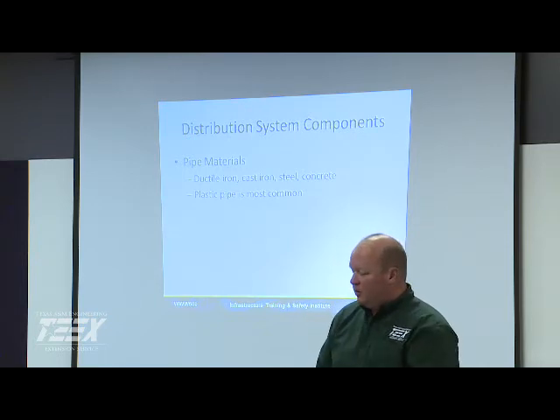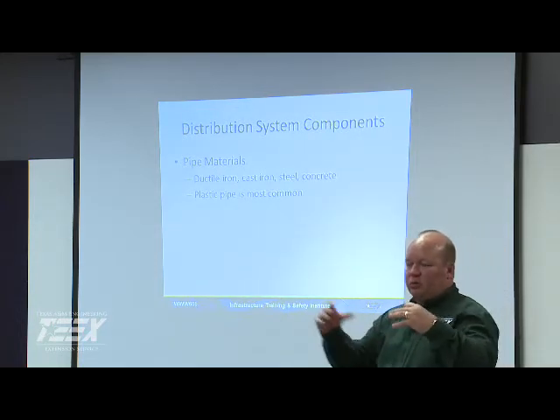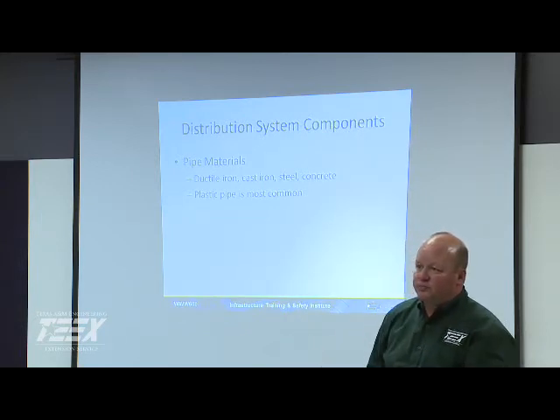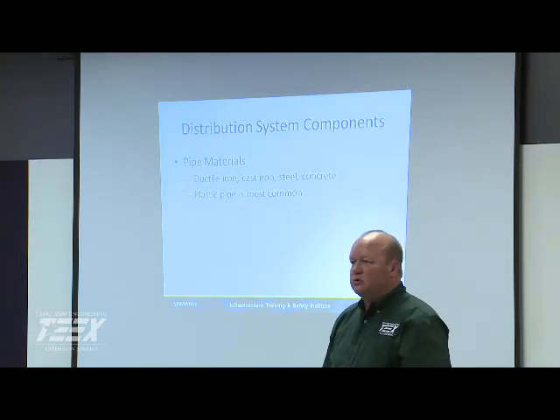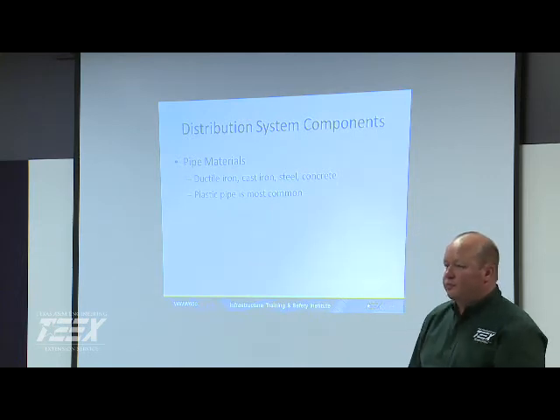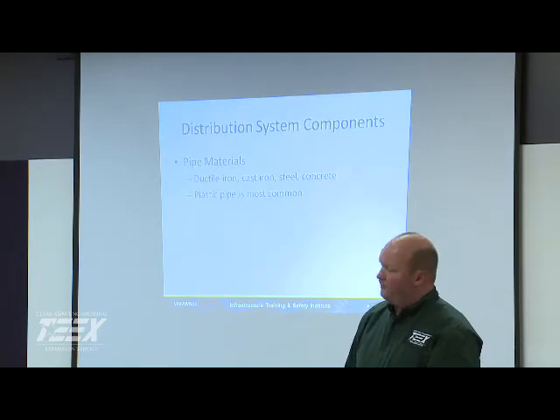We were talking in another class out in Middle Tennessee about the temperature differences, how that's affecting some of it when you're tying in on your taps and stuff like that. I don't know if you all have experienced any of that. Well, if it's cold, it's hard to put a tap on there. It's got a certain temperature. Okay. That's another good factor of the poly, because when you put the saddles on, it ain't a mechanical fit anymore. It's bonded to the pipe. All one. And if it's properly done, the only way it can come off is if the machine tears it off.